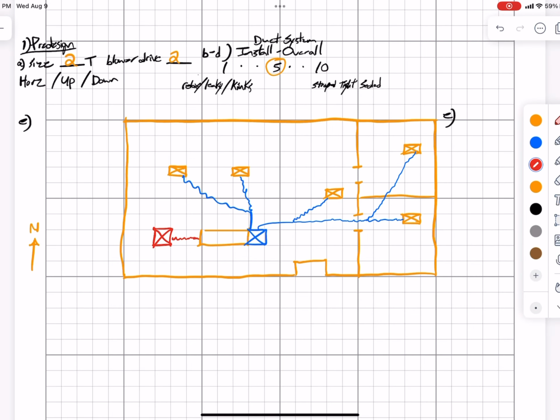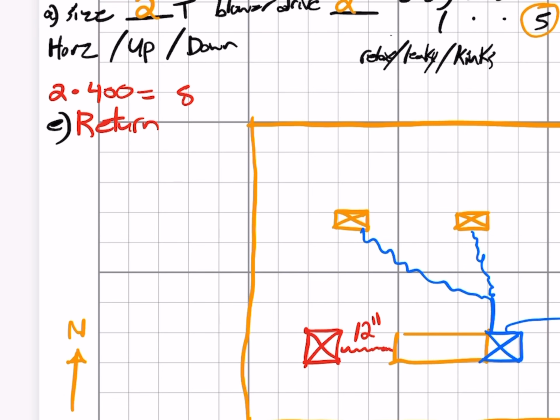It is very important to notate at this point, our only concern is going to be with what is connected to the plenum. We had 1 12-inch return and 2 8-inch supplies. Calculate your required CFM for a 2-ton. 2 times 400 equals 800 required CFM.